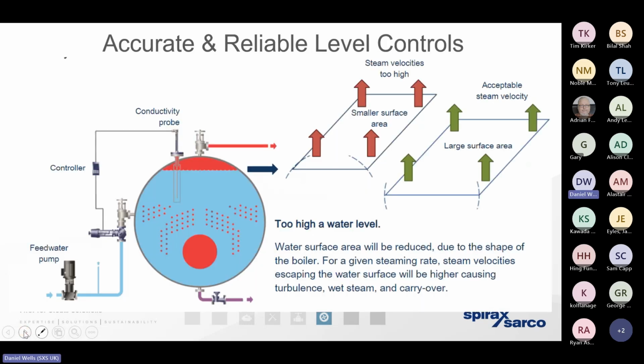Level controls are also an interesting one. The biggest purpose of the level controls is to ensure that the water level doesn't fall to a dangerously low point where we could have a catastrophic incident. So it needs to be capable of sending a signal to a burner to shut off the steam production. The other purpose is, well, if we think of a steam boiler, think of it as being a can of Coke. It's a horizontal vessel. So if we fill that can of Coke 75% full, we lie it on its side, well, we know exactly where the water surface area is.